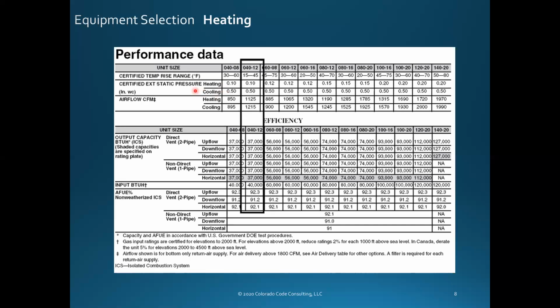So the takeaway from this is, what you don't want to say is, well, the maximum external static you can have for heating is 0.1, and the maximum you can have for cooling is 0.5. That is simply not true. It is false. It is simply what they test it at, okay? You get plenty of designs at 0.7 and 0.8 external static, and you will understand why if you listen to this wonderful program next week. That's when we talk about Manual D.